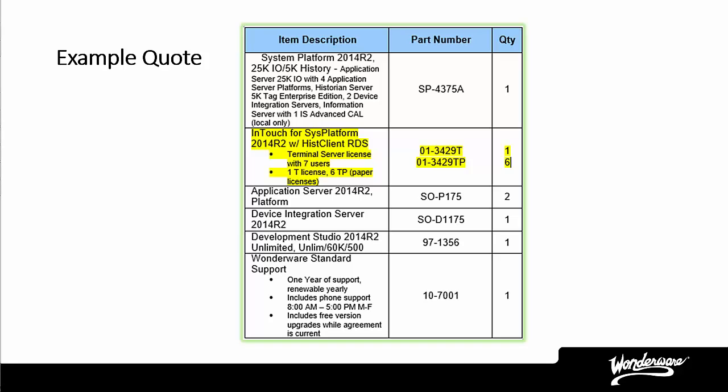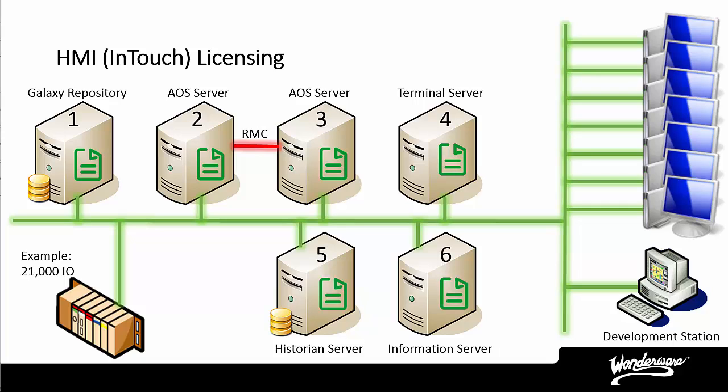Now let's go back to our example quote. In our example architecture, we have chosen to use a terminal server and thin clients to provide the HMI application to the plant floor. On the quote, you will see one or more lines similar to the one highlighted. In this type of architecture, Wonderware licenses the InTouch for System Platform software on the terminal server, and this allows the specified number of thin clients to connect and run the HMI application. This license is placed on the terminal server where the thin clients connect. If you have chosen to add a redundant terminal server, you can purchase a Wonderware InTouch for System Platform RDS Failover license, and that will be put on the redundant terminal server.